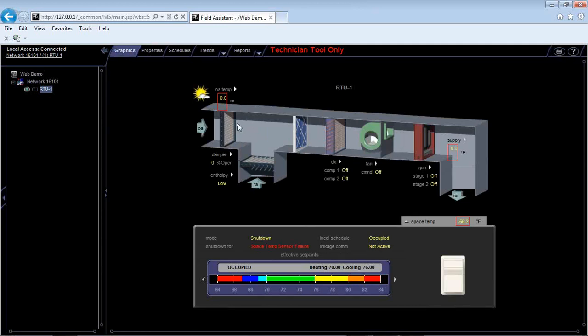Now I say gas, and I have my outdoor air temperature for my economizer monitoring. You can see I have low enthalpy as well. The carrier rooftop unit control for economizer is supposed to run off of enthalpy. If you don't have an enthalpy sensor, it can still run. You just need to make sure that that value reads low so it'll run off temperature the whole time. But its standard comes from the factory ready to go reading off of enthalpy for outdoor air.